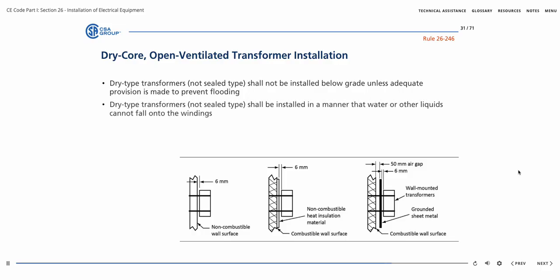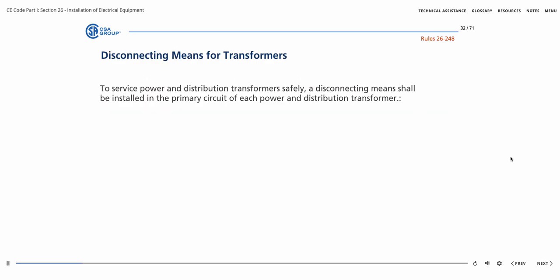Dry-type transformers not of the sealed type shall be installed in such a manner that water or other liquids cannot fall into the windings. The Rule 26-246 also requires that transformers other than the sealed type are to be placed where they are not subject to damage by water. To service power and distribution transformers safely and without interruption of other loads, a disconnecting means shall be installed in the primary circuit of each power and distribution transformer.